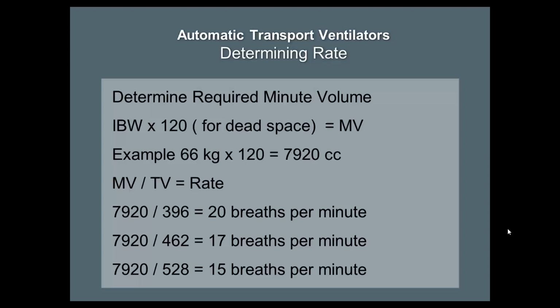So how do we figure it out? Okay, we got how much the tidal volume is, so we need to determine how many times a minute we need to set our rate at. What we're doing here is minute volume divided by tidal volume will give you your rate. So there again, I start about the middle, and I do my 7,920 minute volume divided by the tidal volume, which means I want to set my rate at around 17 times a minute. And you see how you can adjust your rates or your tidal volume.